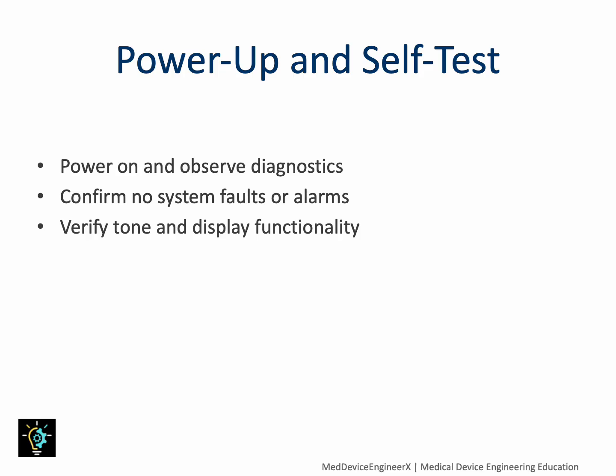When the FT10 powers on, it automatically runs internal diagnostics. Watch the progress bar and ensure the boot sequence completes without error codes. The screen and audio should respond immediately. These checks confirm the microcontroller, sensors, and user interface are functioning properly. If you see any persistent alarms, the test sequence stops here until resolved. A clean startup indicates that internal systems are stable and ready for calibration level verification.